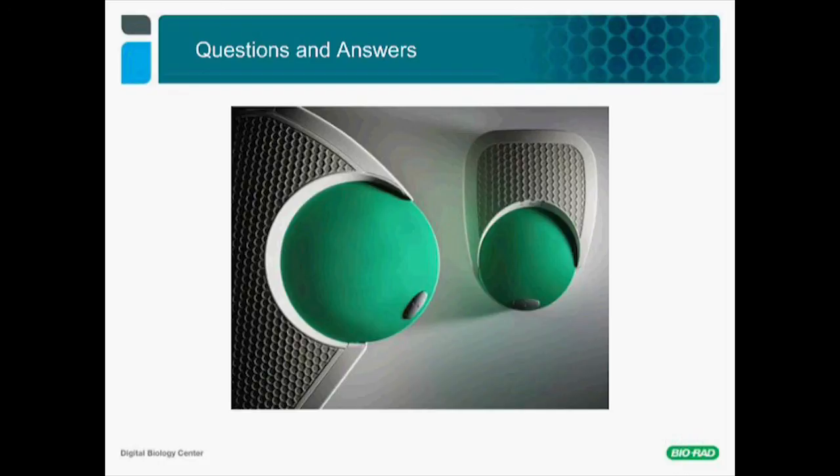We have a question regarding the droplet reader: is the principle the same as flow cytometry? It is very similar—the droplet reader is extremely similar to a flow cytometry readout, except that instead of an aqueous solution, the droplets flow in an oil solution. The principles are very much the same.